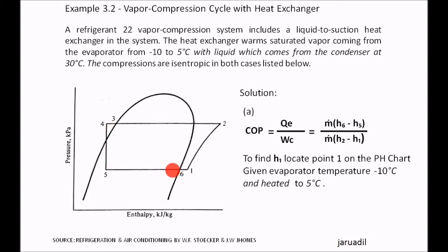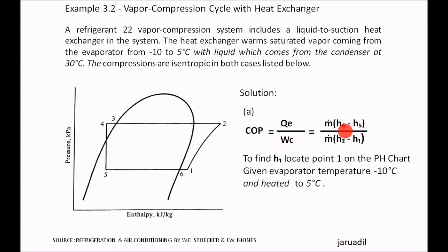1 to 2 is compression. The COP definition remains the same: QE — refrigerating capacity — divided by the work of compression. The refrigerating capacity is mass flow rate times the change in enthalpy from 5 to 6, or H6 minus H5. While the work of compression is mass flow rate times H2 minus H1. The COP equation has not changed. To find H1, locate point 1 on the pH chart given evaporator temperature negative 10°C and heated to 5 degrees Celsius.